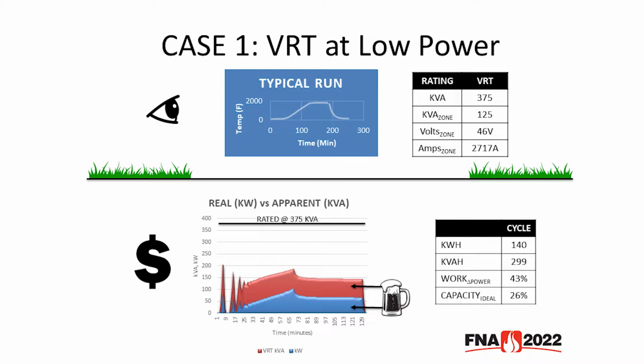The best way to understand this is to compare the total kilowatt hours with the total kVA hours, shown in the table below. Impressively, only 43% of the power in this run is actually doing work. That's about 60% foam on top of the beer. The essential trend here is that with a VRT, the more a furnace is used under its rated electrical capacity, in this case at 26%, the more inefficient it is electrically, and these inefficiencies impact the bottom line.